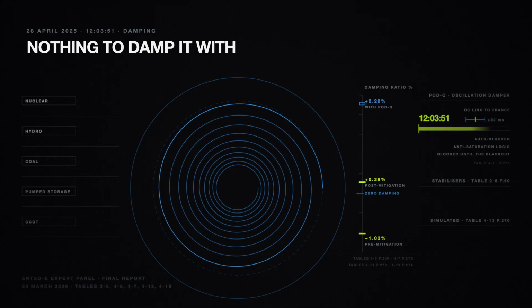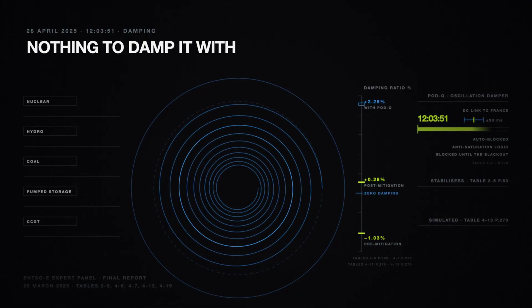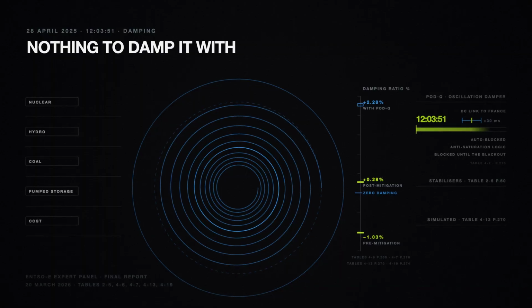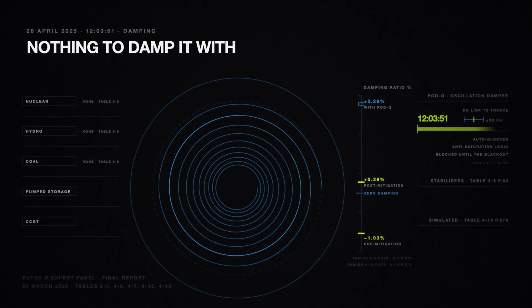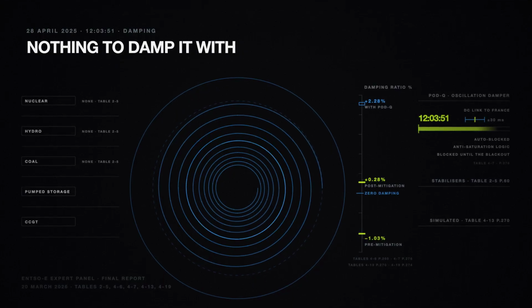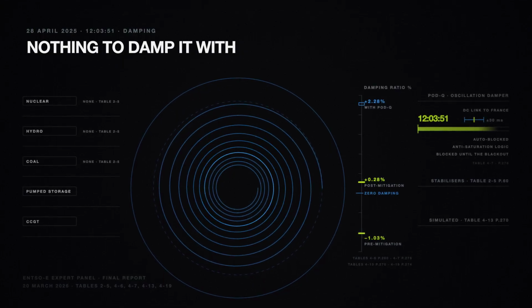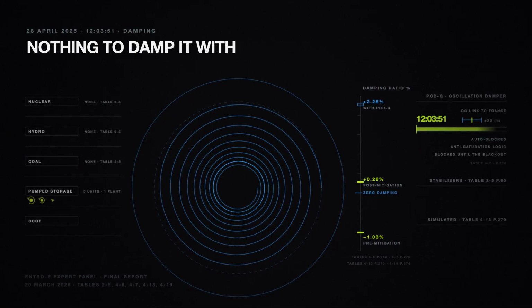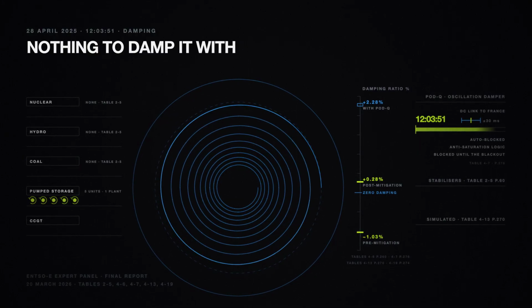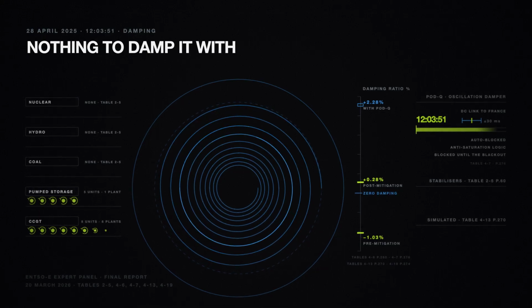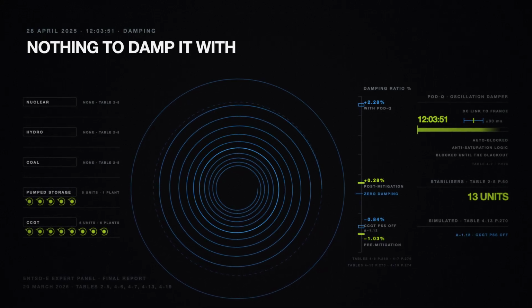Then the machines. A power system stabilizer is a control loop on a generator that damps this kind of swing. Table 2-5 lists which Spanish technologies have them. Nuclear no, hydro no, coal no. Pumped storage, 1 plant 5 units. Combined cycle, 6 plants 8 units. 13 units in the whole of Spain.